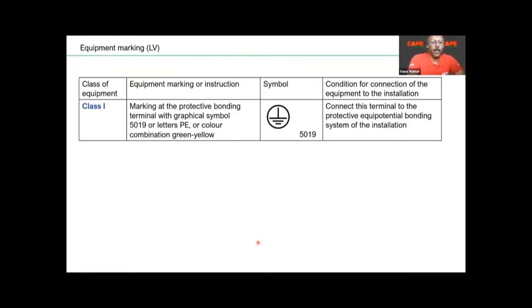Equipment are classified into class 1, class 2, class 3. Class 1 is an equipment whose body, for example a motor or a panel board, will experience a voltage during an earth fault. It is denoted by either the number 5019 or the letters PE or the color combination green and yellow. Basically, the class 1 equipment has to have a terminal marked in this way, or with the symbol 5019. What does it mean? Connect this terminal to the protective equipotential bonding system of the installation. That particular equipment having this marking must be connected to the protective equipotential bonding of the installation.